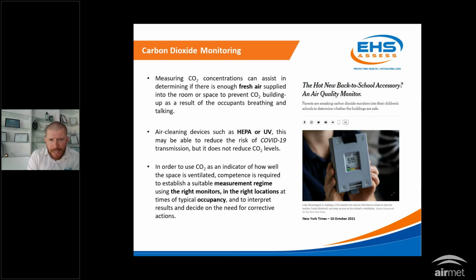Jumping back to carbon dioxide monitoring, a key thing to consider is air cleaning devices. A HEPA filter or UV device that may be installed will have no effect whatsoever on reducing CO2 levels. So you may go to great lengths to have controls in place to capture the virus, then monitor your CO2 levels and find that while your virus controls are very good, your natural ventilation and CO2 levels are really high. So it's really important to get sound advice on a suitable measurement regime, the right type of monitors, where to install them, and occupancy in rooms. All of this needs to be considered before you rush out and install these units.